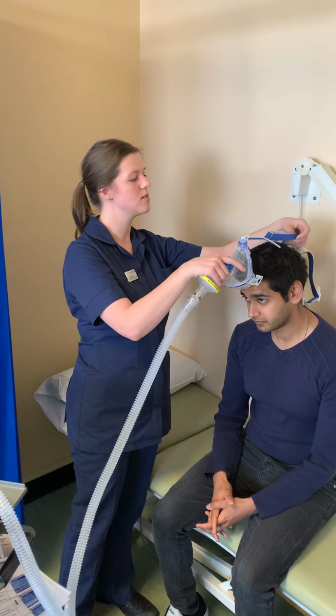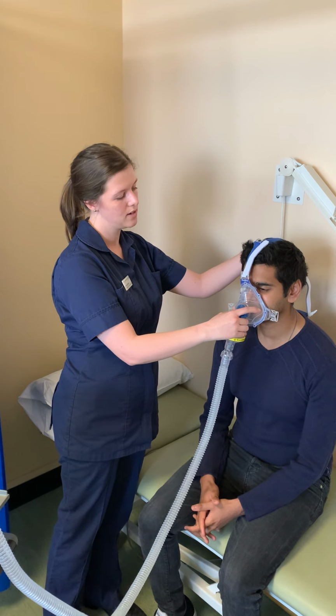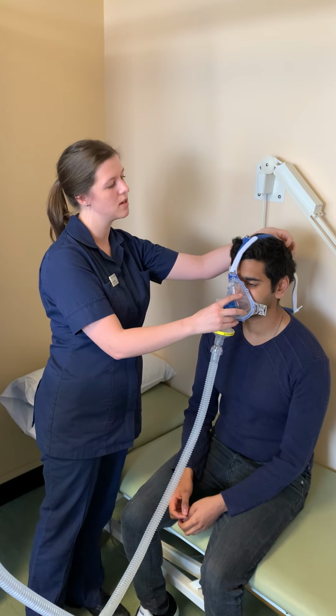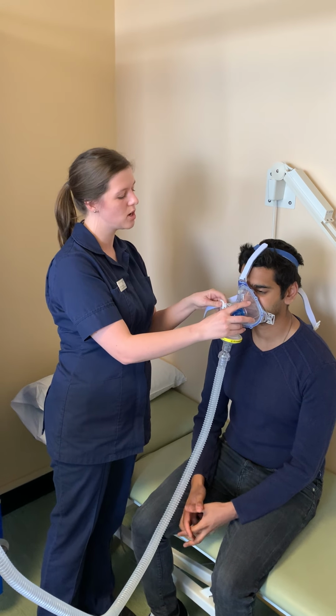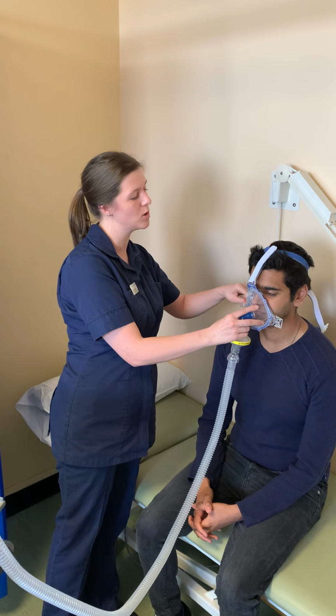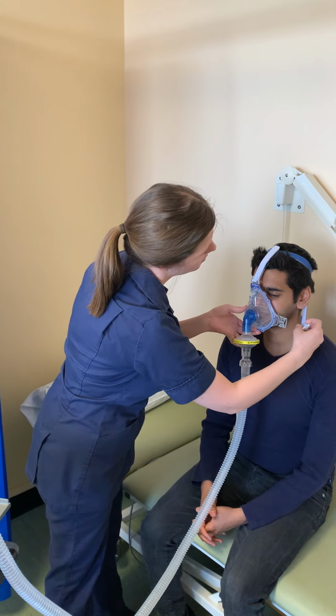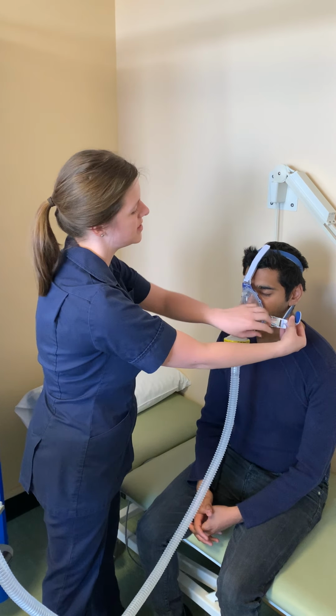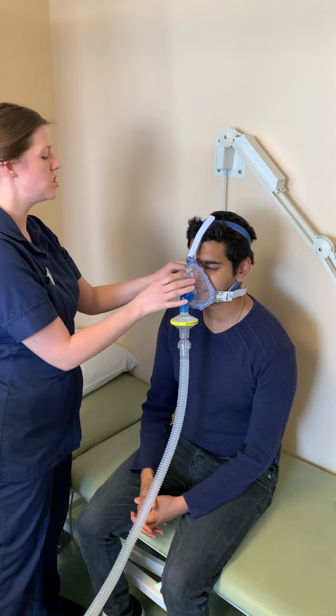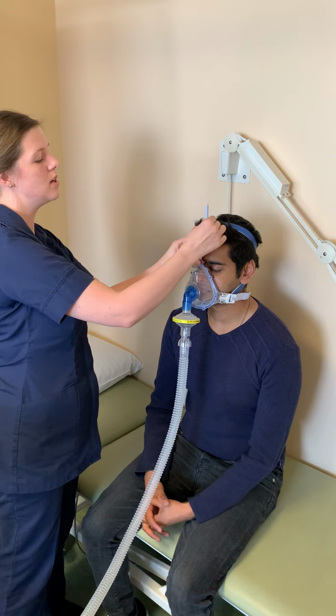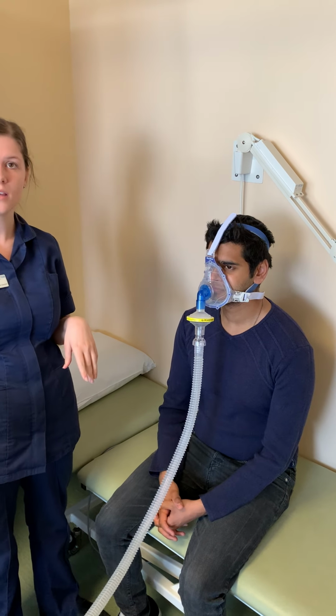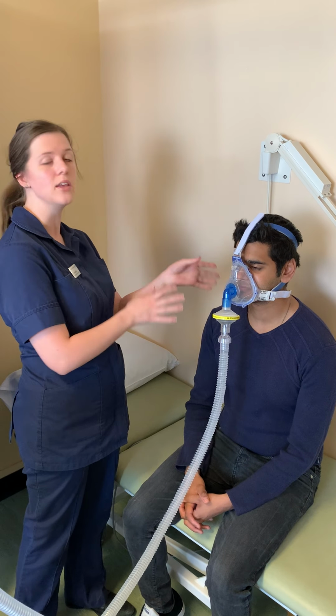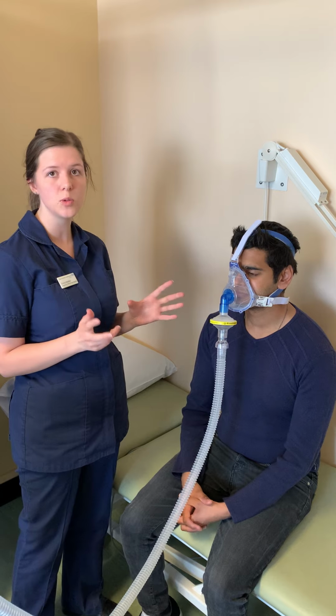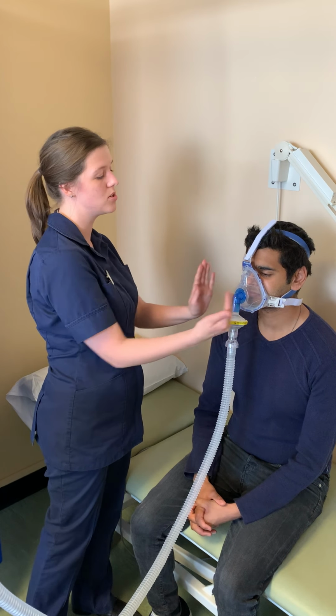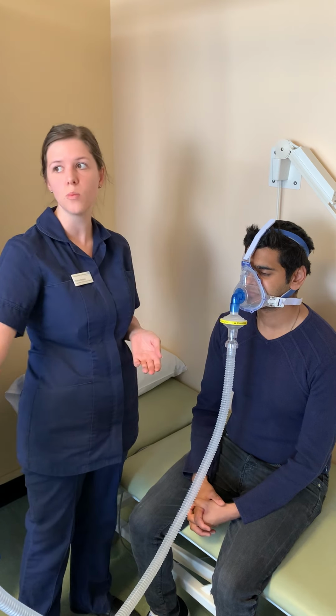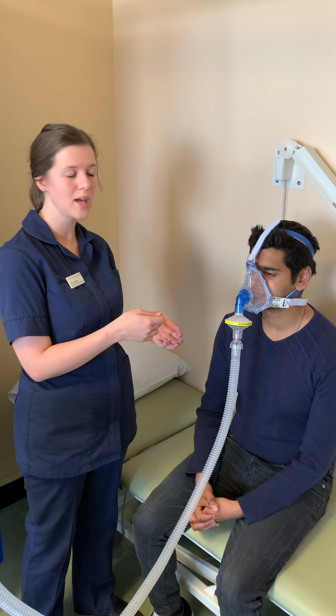So first of all, I'm going to put the mask over his face and I'm going to place it here. It's really good if you just get a seal of where you're putting the mask and then do it. If it's your first time doing it, I would recommend doing it in 2s because it can be a bit hard when you're not used to doing it. So you're going to put it in both ways here and then you're going to tighten. You don't want it to be too tight, but you want it to be tight enough that you're going to get a good seal. So it might be practice, it might be that you start the machine, you can see there's a leak, you stop the machine and you readjust it. A good thing to do, I know it's hard with gloves, but if the machine is leaking, feel around, find out where the leak is, so then when you stop the machine, you know where to readjust. Okay, comfortable?